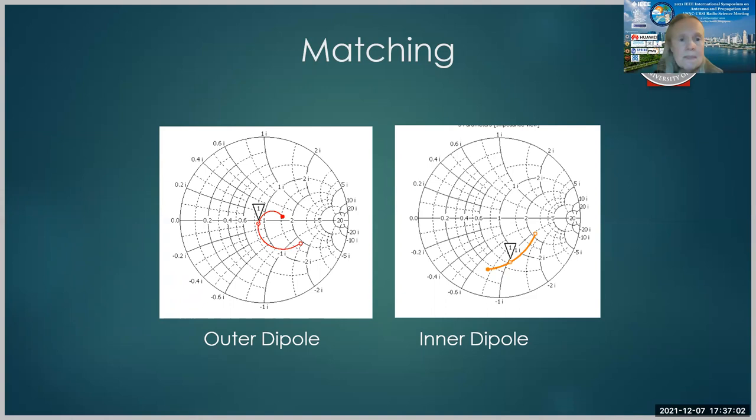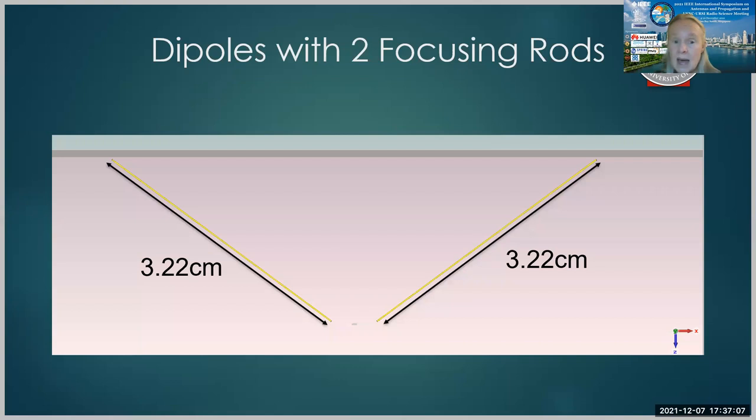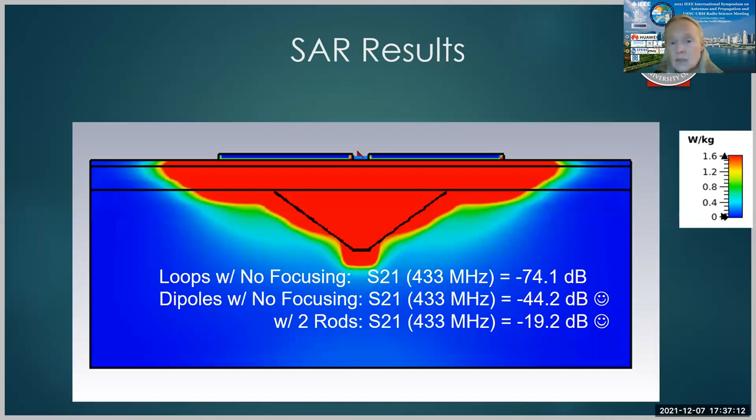Now let's see what would happen if we use the internal and external dipole and we add focusing rods like the polymer rods that we've mentioned before. So in this case, we can see that there is some concentration of power at the location of the implant. And in fact, we see a substantial improvement.